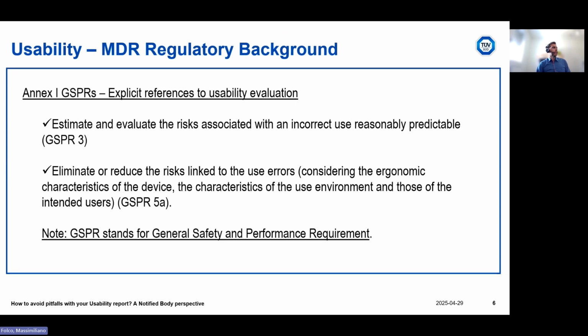Then I included here a list, just for having an idea of which are the explicit references to usability aspects to be considered in the design development and in the preparation of the technical documentation for MDR medical devices that are described in MDR. This is a difference with respect to MDD, where usability was not so explicitly mentioned, while in MDR we have several points, several requirements regarding explicitly usability.